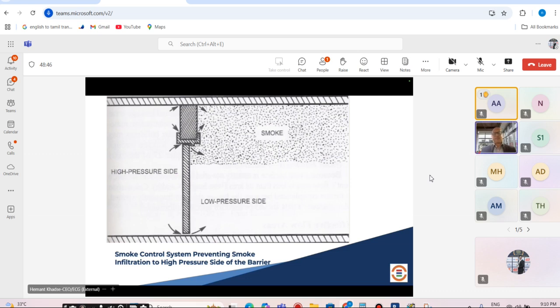Same as the case when you pressurize the lift well: you are also going to create the differential pressure inside the well, so that the well will not have an ingress of smoke or smoke infiltration, and the lift well also will not transfer the smoke into the lobbies, which makes the egress difficult for human safety. So fundamentally, you are using that differential pressure technique.